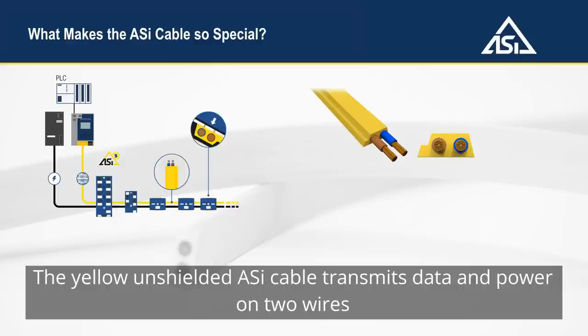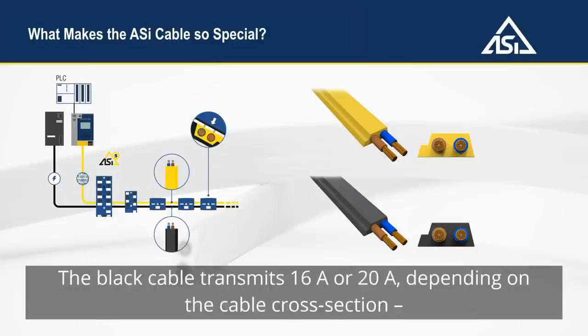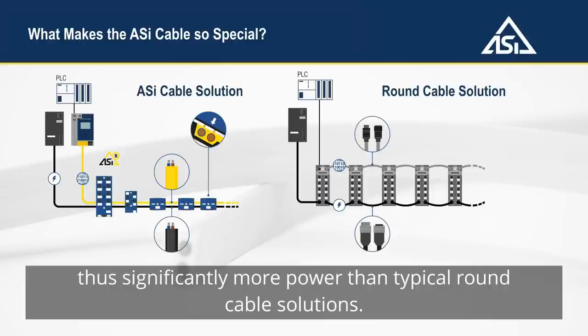The yellow unshielded ASi cable transmits data and power on two wires and offers many advantages compared to conventional round cables. The black cable transmits 16 amps or 20 amps depending on the cable cross section, thus significantly more power than typical round cable solutions.